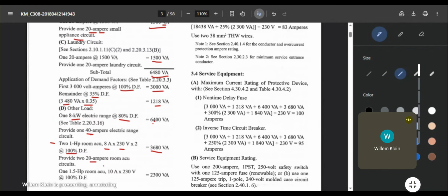So you'll provide two 20 ampere aircon circuits. Take note of this: even though they are the same 1 HP and they are included in one computation, you will still use separate branch circuits for each 1 HP aircon. You can't use one circuit containing two aircon units. Is that clear? So again, one aircon, one circuit breaker. That's the rule, or one motor load, one circuit breaker.